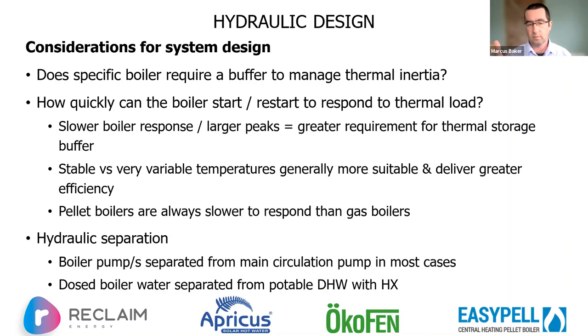And of course, the boilers have got steel water jackets, and so it's dosed, or at the very least, it's black water that shouldn't be being renewed, and so it needs to be separated from domestic hot water, potable water.